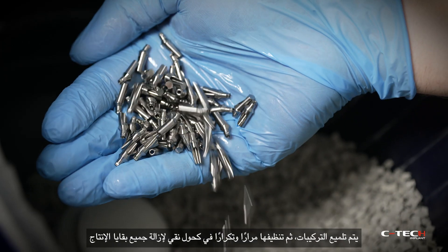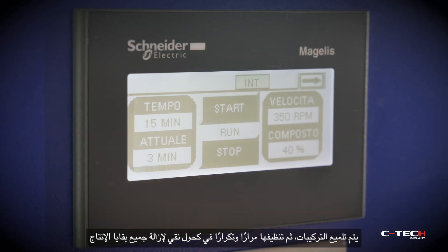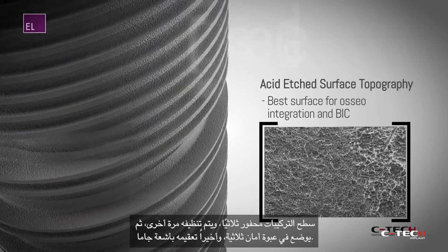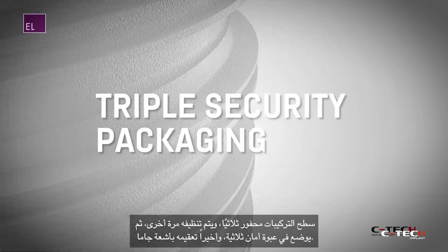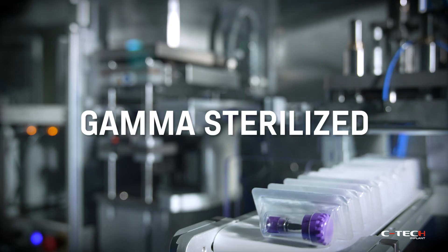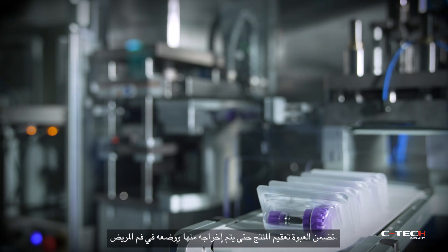The implants are polished, then cleaned repeatedly in pure alcohol to remove all production residues. The surface of the implant is triple-etched, cleaned once again, and then put into a triple-security packaging and finally gamma-sterilized. This packaging ensures their sterility until they are removed and placed into the patient.